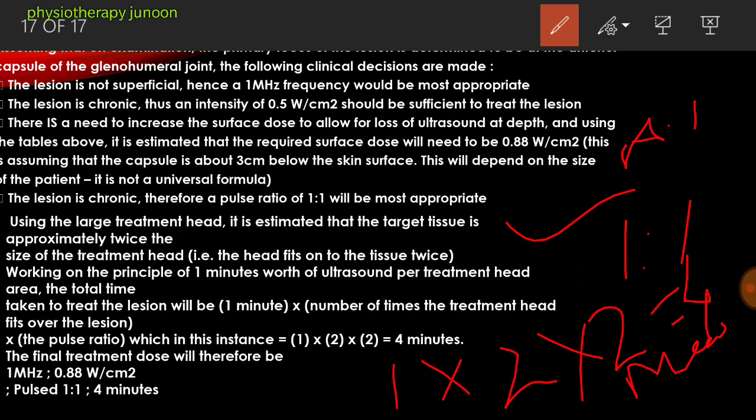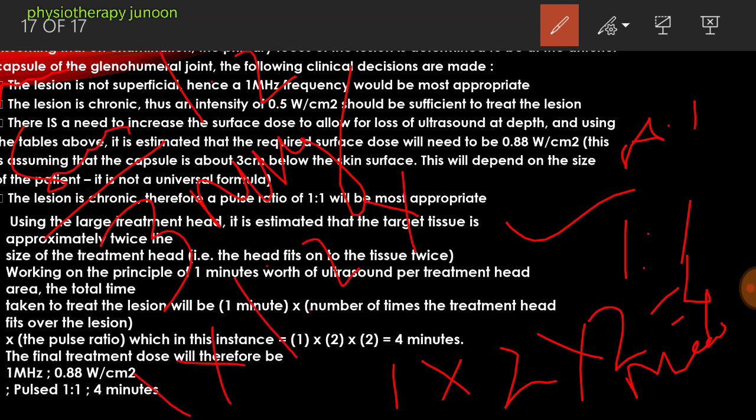The lesion is superficial, so 3 megahertz frequency would be most appropriate. The lesion is subacute, not most acute, not chronic, subacute. So here we use the intensity 1.2.